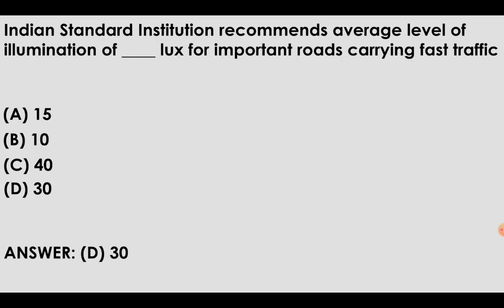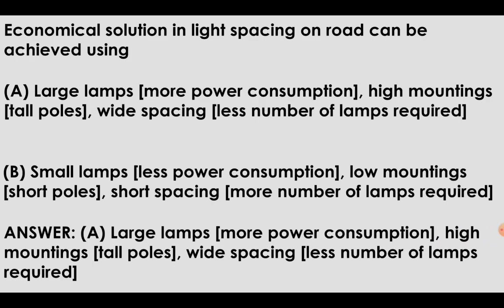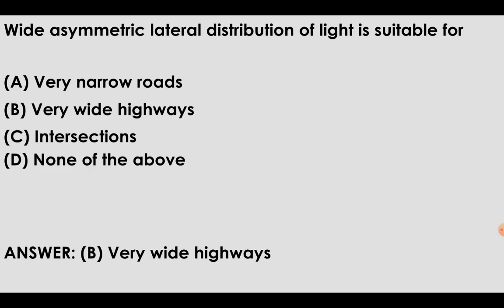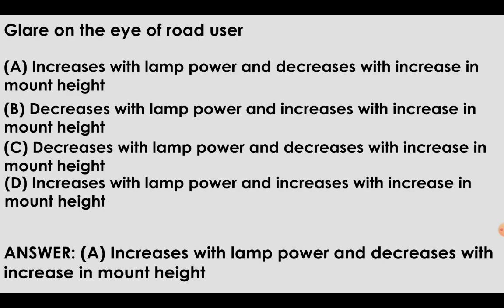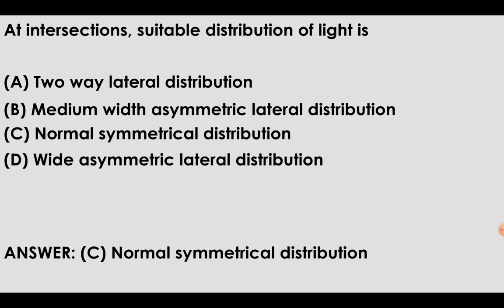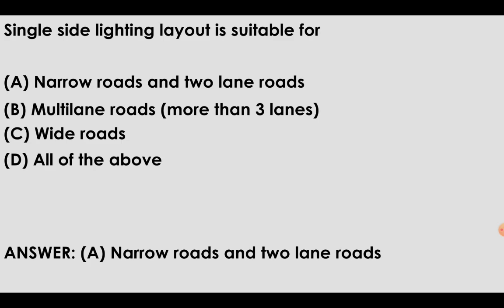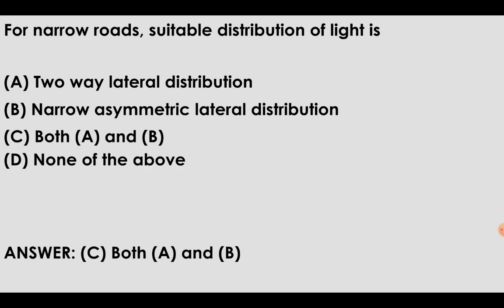Economical solution in light spacing on the road can be achieved by using large lamps, so that they are going to have more power consumption, but high mounting, that's tall pole, and wide spacing, thereby less number of lamps will be required. Okay. Wide asymmetric lateral distribution of light is suitable for very wide highways. Glare on the eye of road user increases with lamp power and decreases with increase in mount height. At intersection, suitable distribution of light is normal symmetrical distribution. Single side lighting layout is suitable for narrow roads and two-lane roads. For narrow roads, suitable distribution of light is two-way lateral distribution and narrow asymmetric lateral distribution.